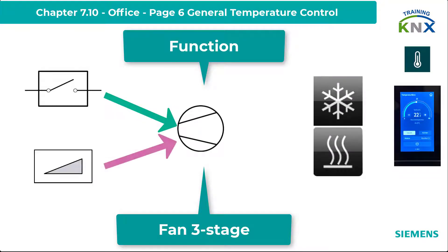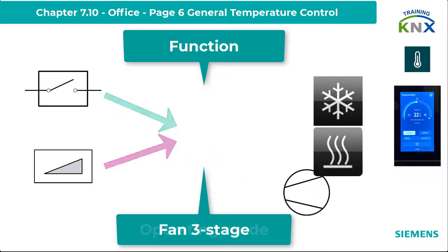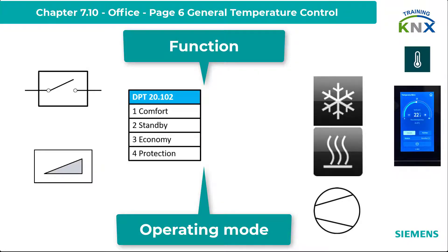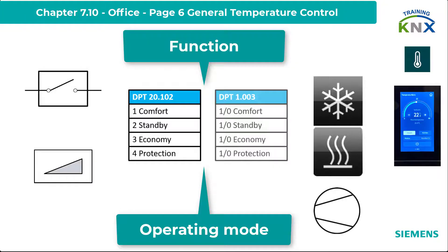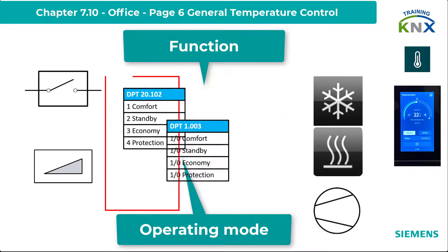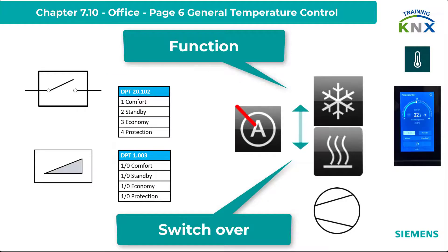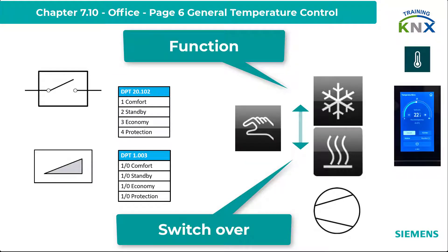The operating mode can be set via the 1-byte object DPT 20.102 as well as via the 4x1-bit objects for the four operating modes, which were used more frequently in the past. Automatic switching between heating and cooling mode is not available; this must be done manually by the user at the panel or via the corresponding object control mode externally.